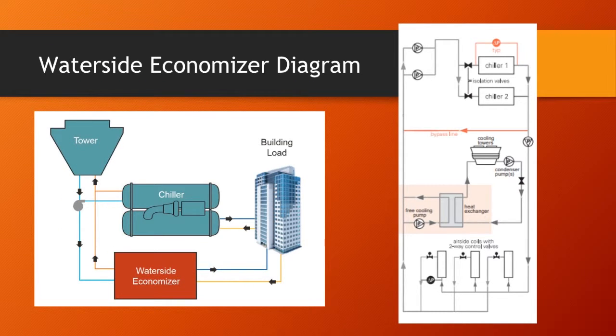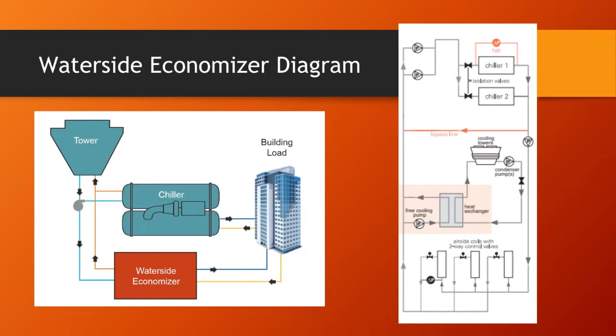The key to making these things very efficient is having the supply temperature coming off the tower lower than the design temperature of your chilled water loop. That will greatly aid the heat transfer. This one over here is in series. That means if you want to run your water side economizer and your chillers at the same time to help maybe lower the chiller load, you'd have to run the heat exchanger on the chilled water return, versus this one, which is in parallel, which means this chiller cannot run when the water side economizer is running. It's either only economizer or only chillers.